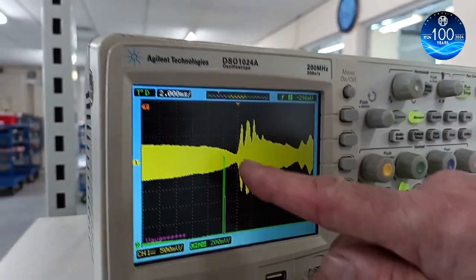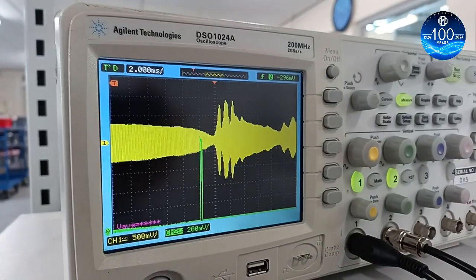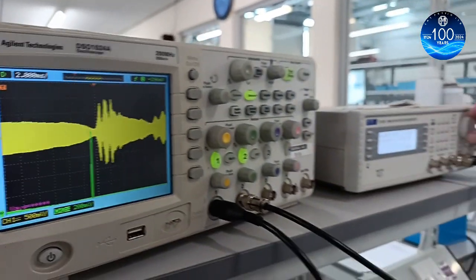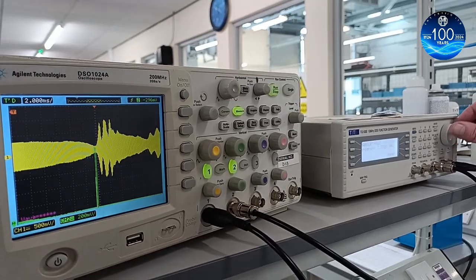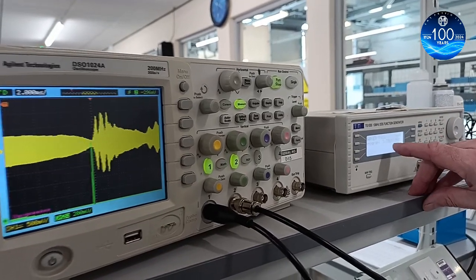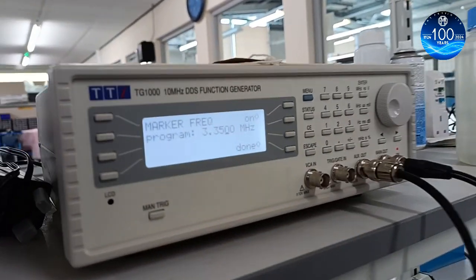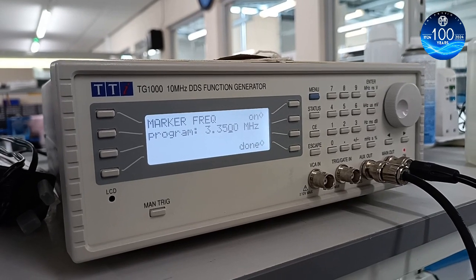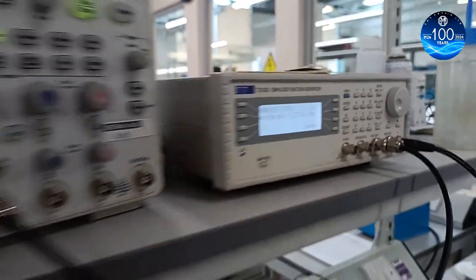It's bonded to that steel with a conductive adhesive which contains silver. We place that on there, and you can see we've got this same resonant point, and we can adjust to line up with that. We're looking for a figure here that is somewhere between 3.2 and 3.5, and we've got 3.350. So that is acceptable and ready to go.